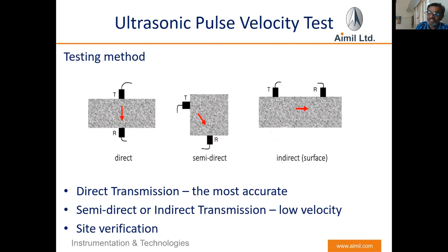People say, as a thumb rule - there is no documented standard for this - that if you do not have access for direct transmission and are using semi-direct or indirect transmission, whatever velocity you get, you have to increase it a little. How much? That can only be decided after site verification. So there is a lot of human intervention involved, but you have to make that judgment based on the application and site conditions.